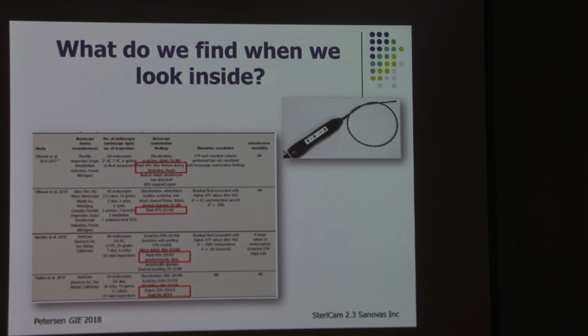The worrisome part is that we find a lot of things there. Highlighted is that in one study, fluid was found 95% of the time, and included cloudy fluid. In half of the scopes something was found, and it seems to be a rate between 20 and 40%. We find retained fluid within the channel of the scope after the high-level disinfection, and that is what leads to biofilm formation.